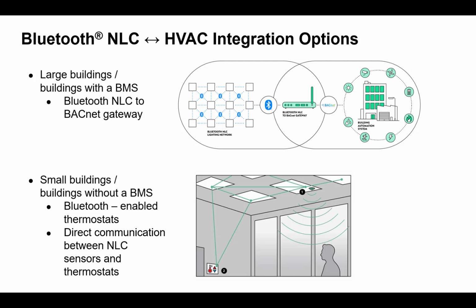It exposes the Bluetooth devices as BACnet objects, on different levels. You can have each individual sensor, like a Bluetooth Mesh occupancy sensor, exposed as a BACnet object, but you can also have a whole Bluetooth occupancy zone exposed as a BACnet object. So there are different levels of granularity possible. From the HVAC perspective, you can subscribe to those objects, use the change of value technique to be notified about occupancy events, and then consume this data.